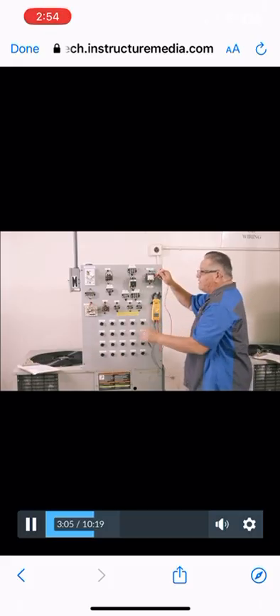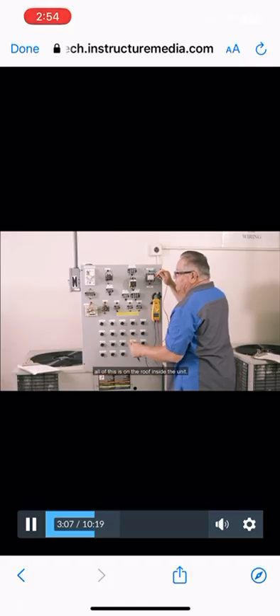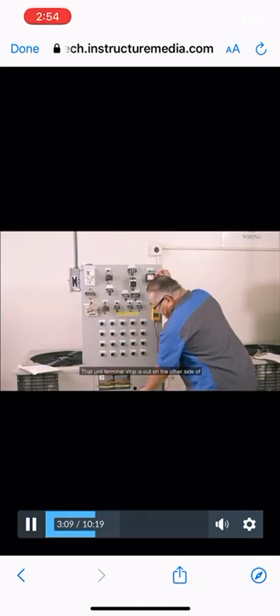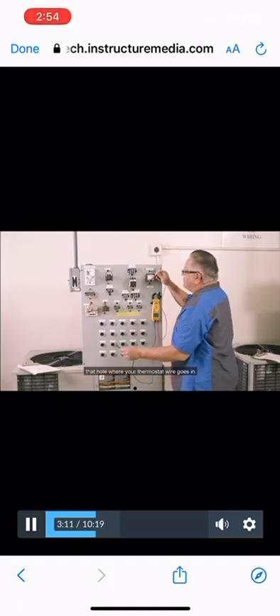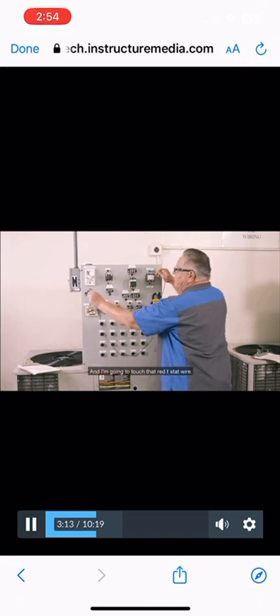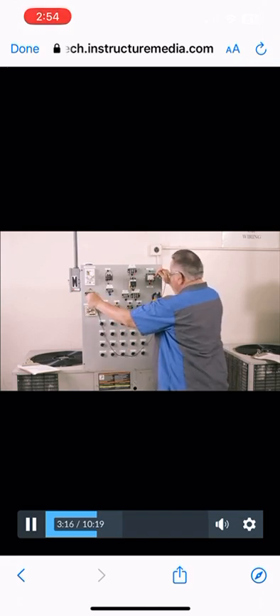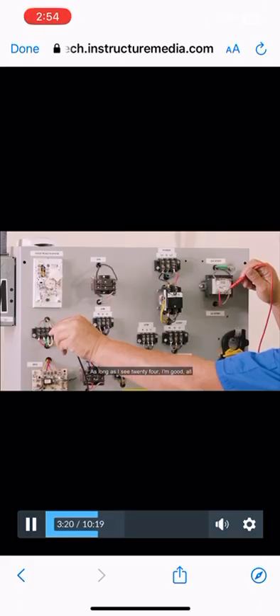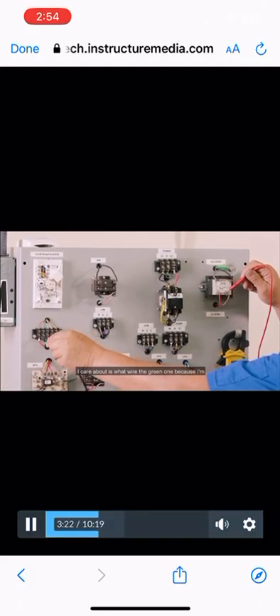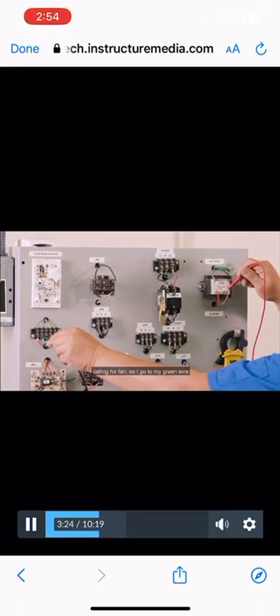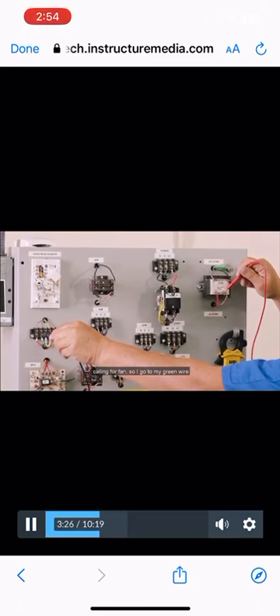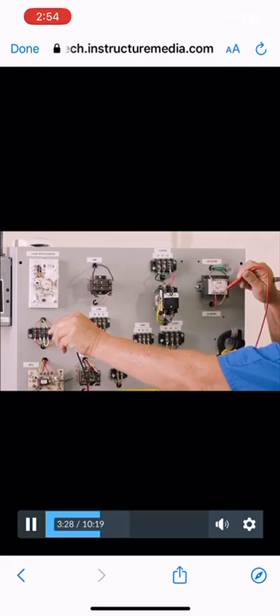I'm on the roof. All this is on the roof inside the unit. That unit terminal strip is right on the other side of that hole where your thermostat wire goes in. And I'm going to touch that red T-stat wire, and I got 24. As long as I see 24, I'm good. All I care about is what wire? The green one, because I'm calling for fan. So I go to my green wire, and I got nothing.